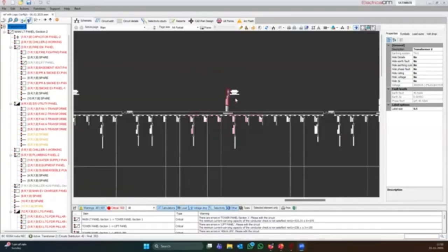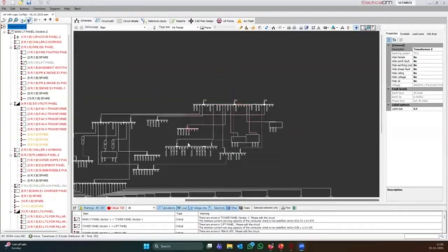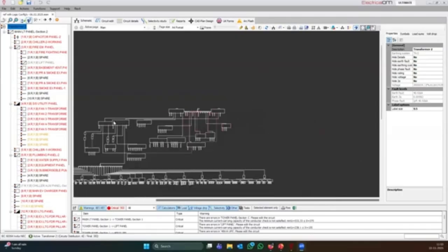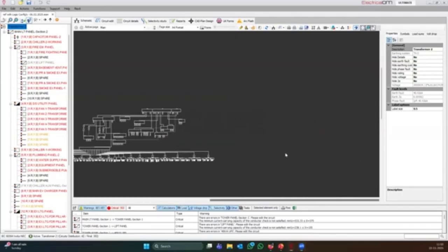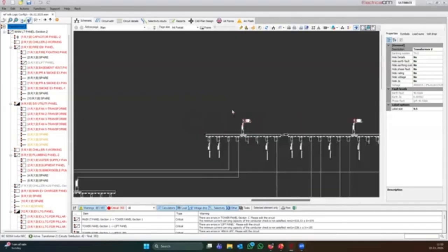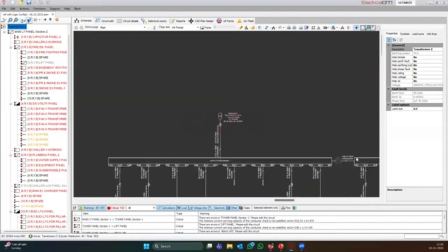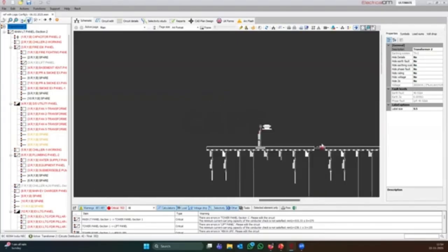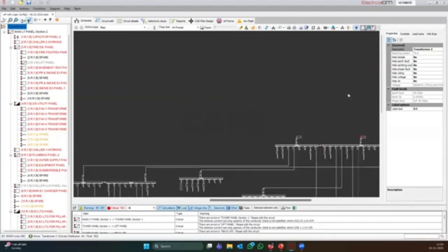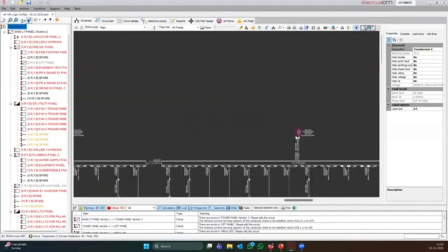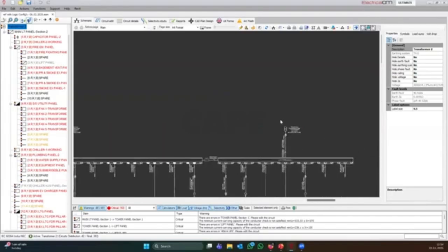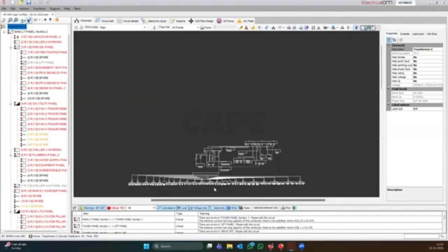So this is a residential complex. I'm only having the common load of a residential complex now, and they have close to three transformers. They are not in parallel, because the bus coupler is not on. You have three transformers, and each goes to its own load, and this is all going to be the common load.